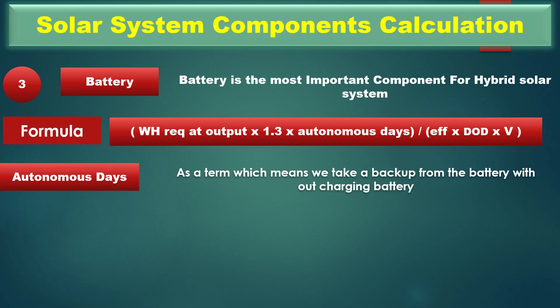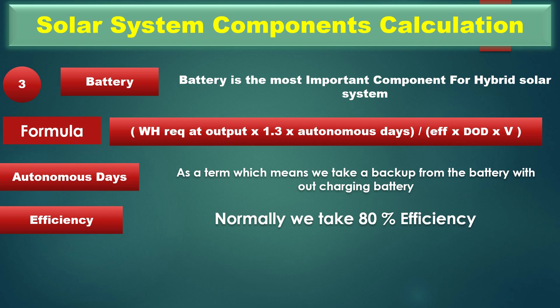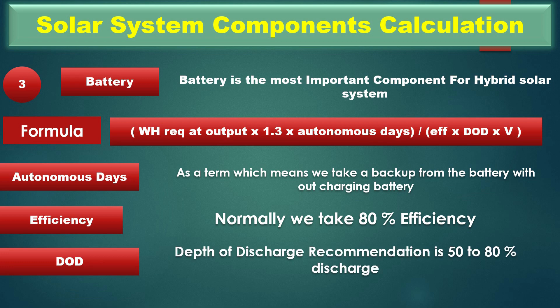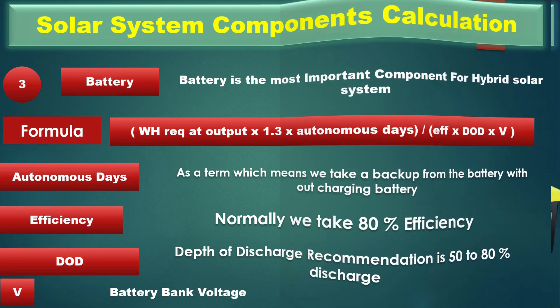Autonomous days means the backup from the battery without charging — if there is no sun and no generator, the battery still provides backup. You can express it in hours or days; if the customer doesn't specify, use a value of 1. Efficiency is normally taken as 80%. DoD (depth of discharge) — battery life depends on cycles; discharging 100% shortens life, so the recommendation is 50 to 80% discharge. V is the battery bank voltage: two batteries in series gives 24 volts, one battery gives 12 volts. This voltage is found in the inverter datasheet — mostly a 2 kW inverter uses a 24-volt system.